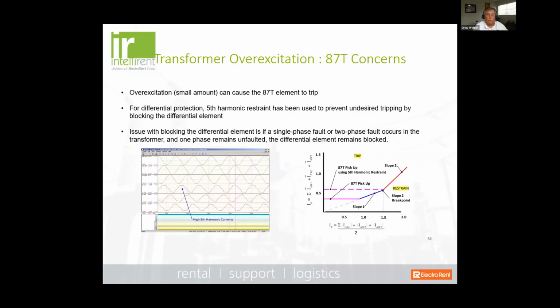Now, if you're a protective relay person, you'll know that a lot of times on a GSU we have what's called a fifth harmonic restraint or blocking. Because when you get into a volts per hertz condition, even if it's not high enough to create a problem, it can create differential current that the relay is going to see. So in order to avoid a nuisance trip on a momentary excursion or a very low volts per hertz, we block the transformer differential from operating by looking at the fifth harmonic content in the current the relay is seeing. That will block the relay from misoperating. But if the volts per hertz gets high enough that it exceeds the limits in the settings, it will trip anyway.